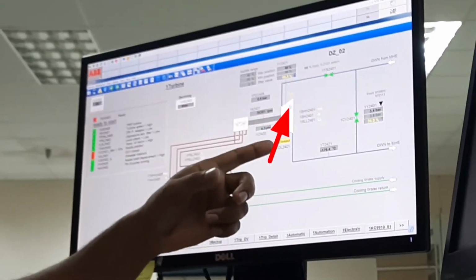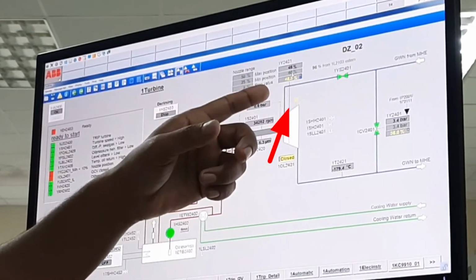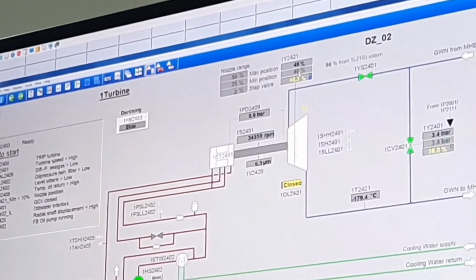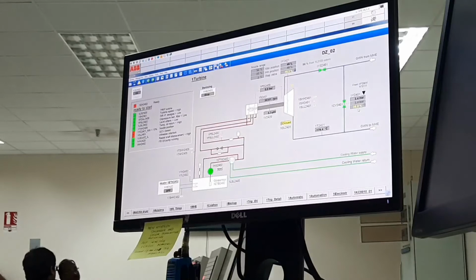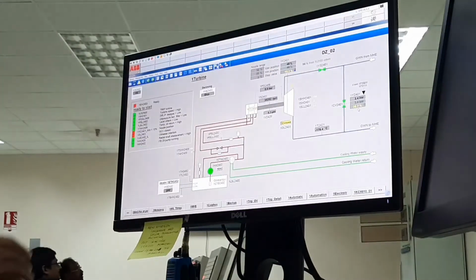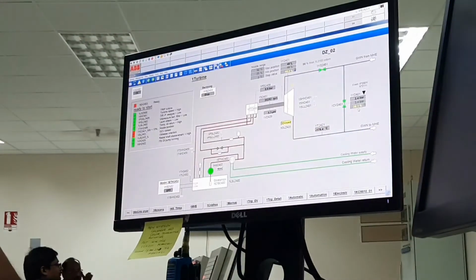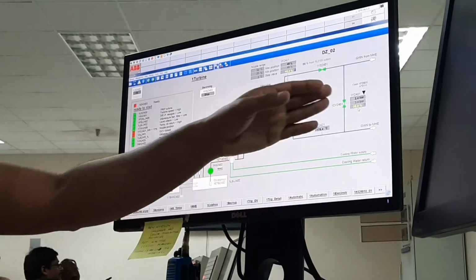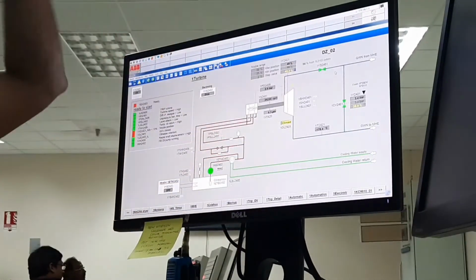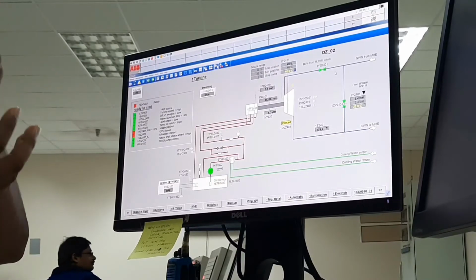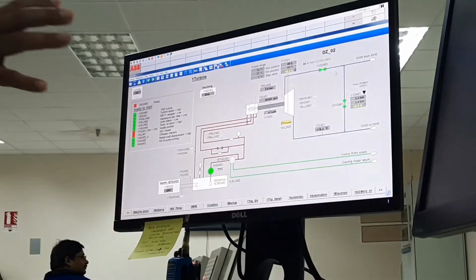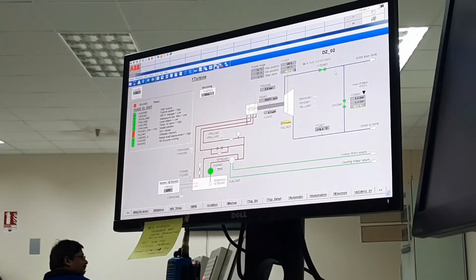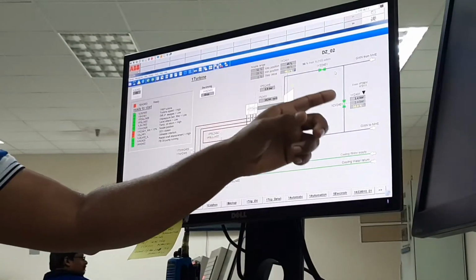At 100% load condition the expansion turbine valve would be fully open, but now the expansion turbine valve opening is only 46%, so it is not 100% open. For that reason this bypass valve is also 36% open, because not all the product comes to the expansion turbine; the maximum product comes to the expansion turbine, and some product goes through the bypass valve to maintain pressure. If you close this bypass valve, the expansion turbine inlet pressure will increase, because the expansion turbine valve opening is small but more product comes, so pressure will increase. It will be a big problem. For that reason, we need to continuously keep this expansion turbine bypass valve open at least a minimum of 5%.